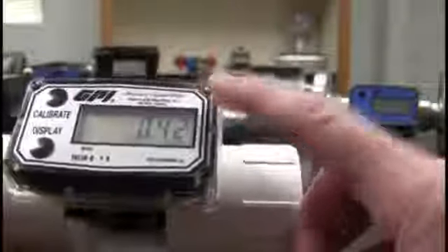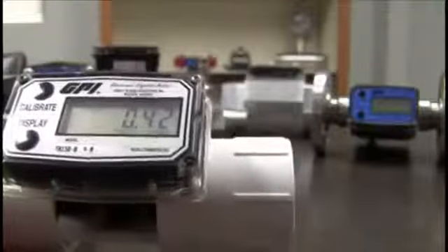Now the display creates a magnetic field, which you can see with the magnet right about there. And that magnet creates a magnetic field, so as the turbine spins, when fluid goes through the pipe, it spins that turbine, and you can see right about there, it's a little metal hunk in the end of the turbine. So each time that metal hunk breaks the magnetic field, it creates a pulse, and then of course the display counts it. And the display has already been programmed by a calibrator to know exactly how many pulses equals a gallon. And that's really about it with a turbine meter.